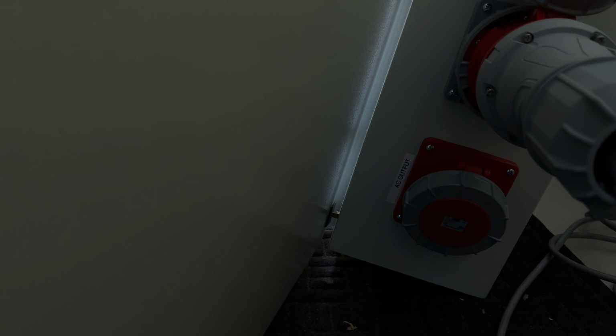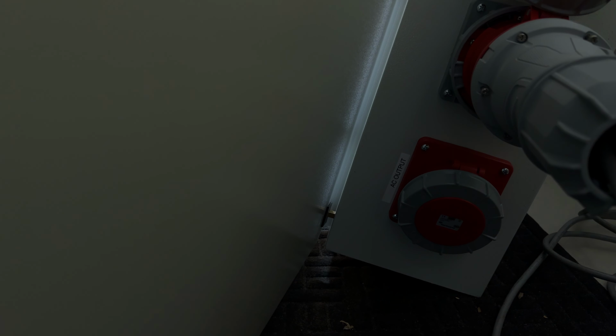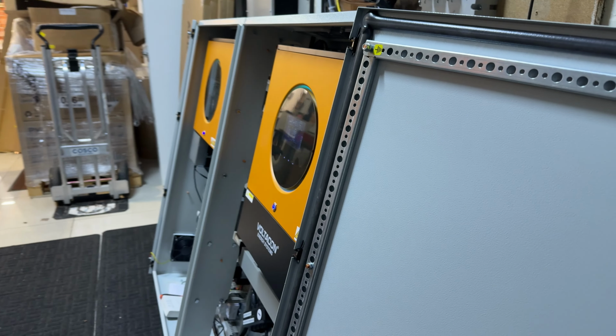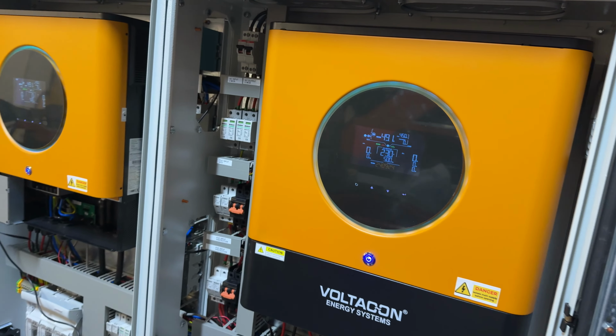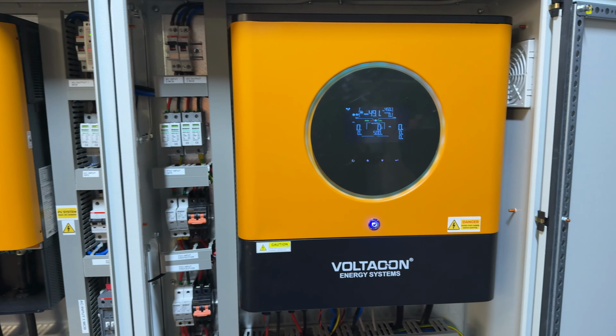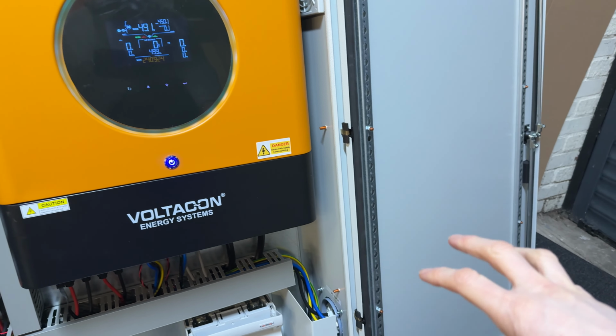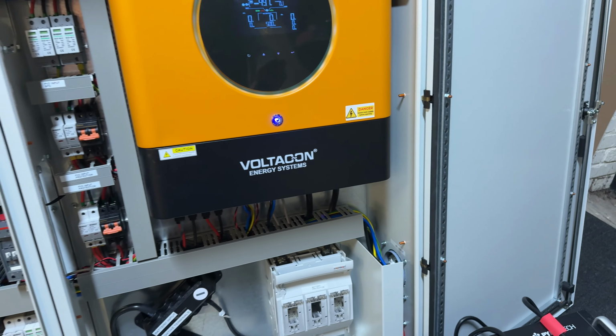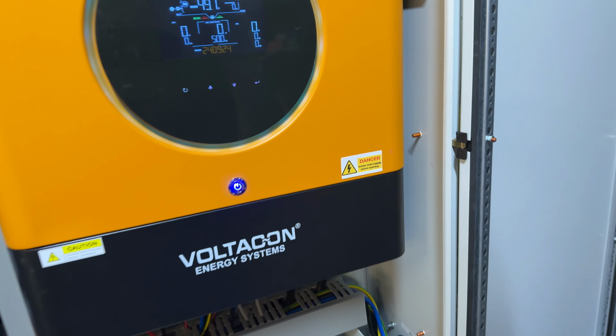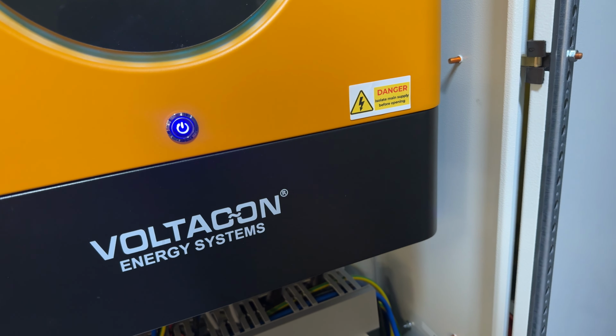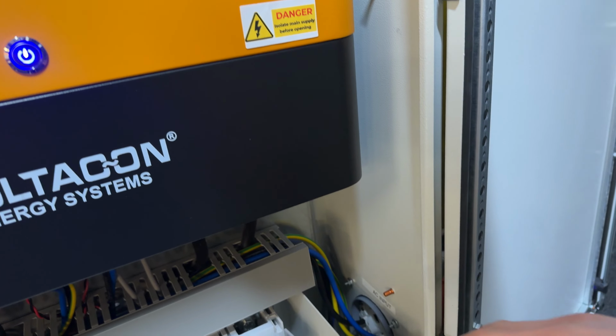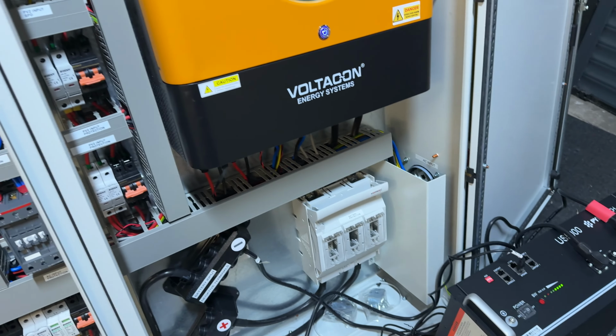The bottom socket is the AC output, a 16 kilowatt AC output. And this output is connected back to the consumer unit or the switchboard of your property. You shouldn't connect the input to the output or the output to the input at any time. The two terminals here, the two big red sockets, should always be independent. We don't mix the neutral of the input with the neutral of the output. The two neutrals are completely decoupled.